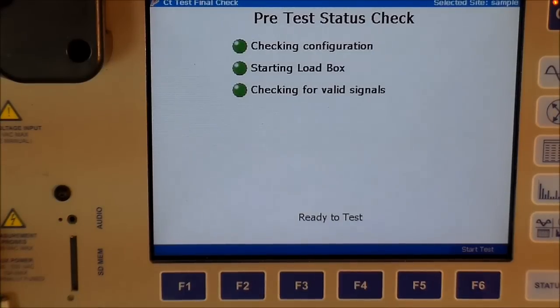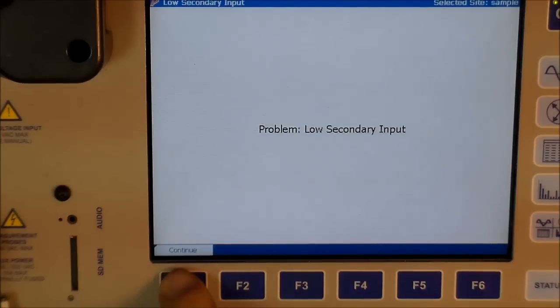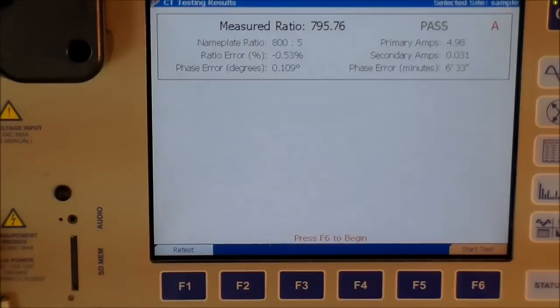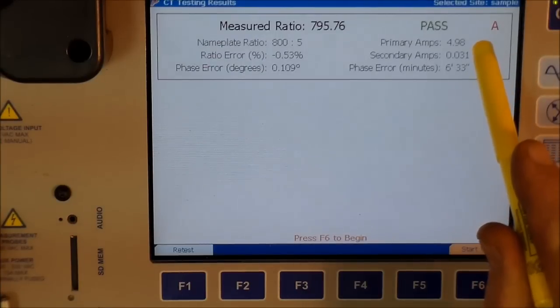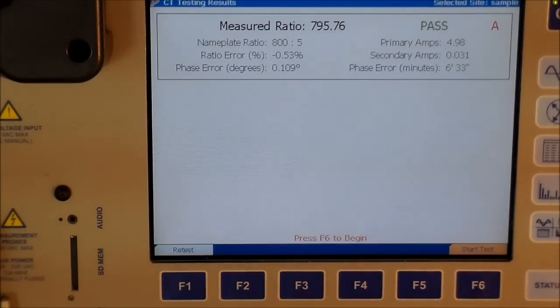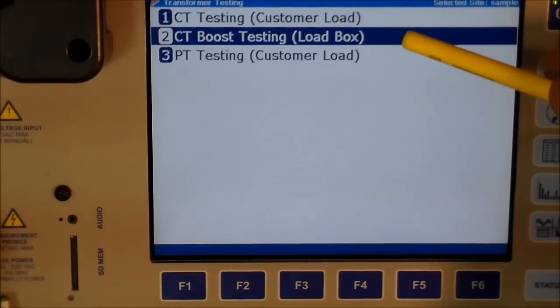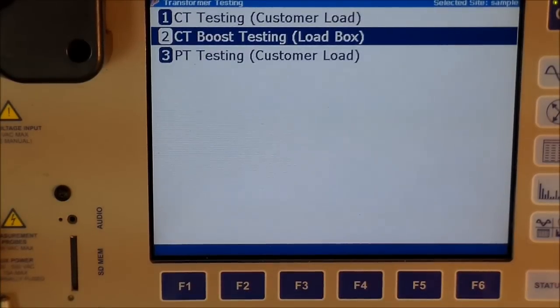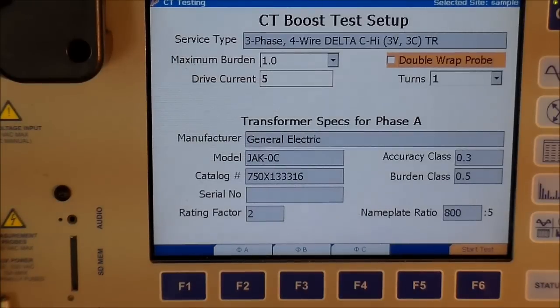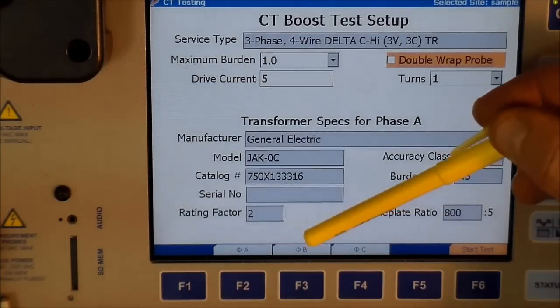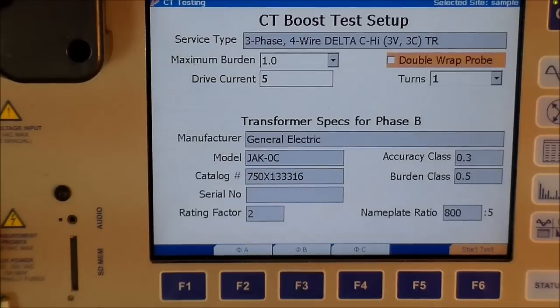And start once more. What's that, 5 or 6 now? And again, the same error, just because we're not driving very much current. But by holding the probe straight, the test passed. Now keep in mind, all of that was just for A phase. If we want to go back and test the other phases, we'll have to hit previous, start all over, go back to CT boost testing, remove all of your leads and connections, put them on B phase, and you press F3 to load the CT data for B phase, and proceed with testing.